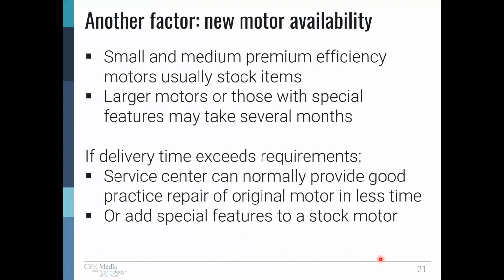Another factor is new motor availability. If premium efficiency motors in 2, 4, and 6 poles, 3,600 RPM nominal, 1,800 nominal, and 1,200 RPM nominal, are available, those motors are probably going to be off-the-shelf items. When we get into larger motors or motors with special features, we can run into some, I don't want to call it issues, but they may not be on the shelf, so there's some delivery time associated with them. If that time exceeds the requirements of the customer, the service center can usually provide a good practice repair in less time than it's going to take to deliver that new motor.